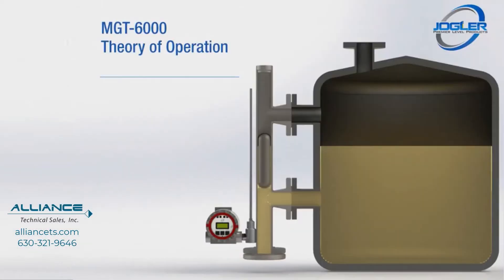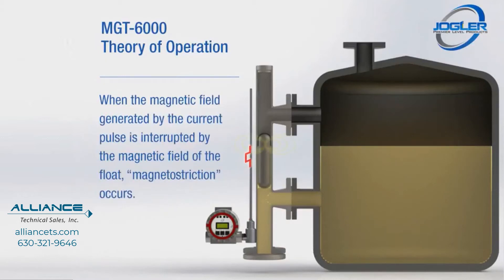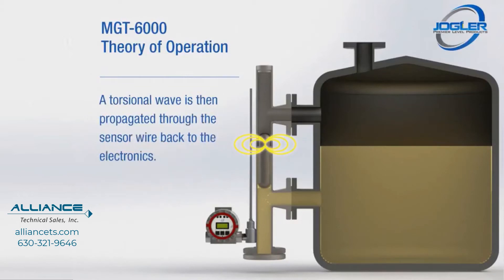The MGT-6000's electronics send a current pulse through the magnetostrictive sensor wire. When the magnetic field generated by the current pulse is interrupted by the magnetic field of the float, magnetostriction occurs. A torsional wave is then propagated through the sensor wire back to the electronics.